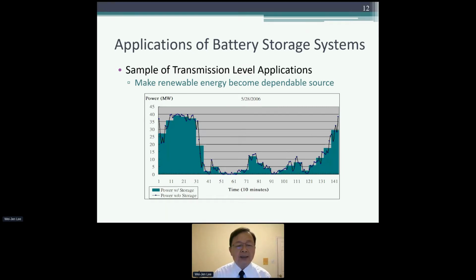With that, if renewable energy can be considered, say for this study, we can put in a small amount of battery storage and try to smooth out the renewable energy and give a prediction. You can tell the operator that for the next 15 or 20 minutes, this is the amount of energy or power I can give you—how many megawatts fixed for that period. This becomes very helpful for the system operator when they perform economic dispatch, because this becomes a dependable source.